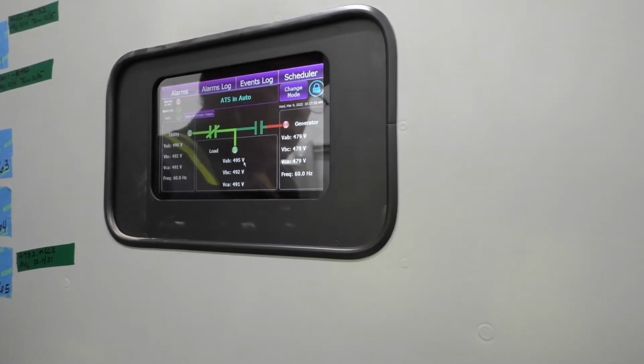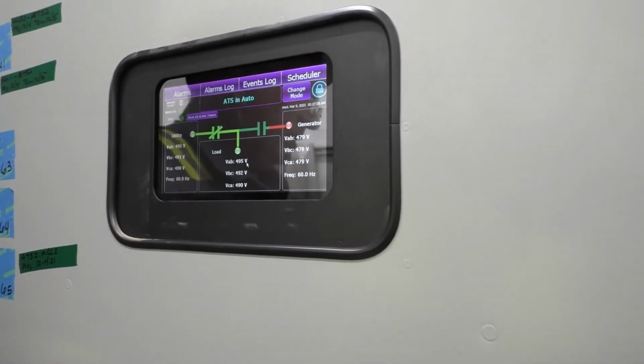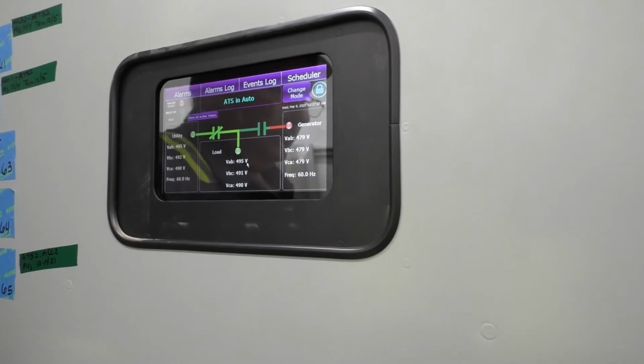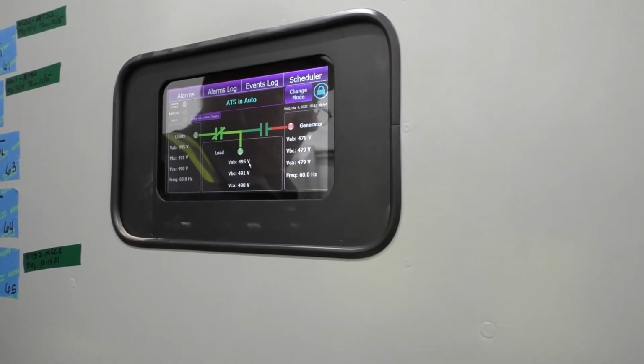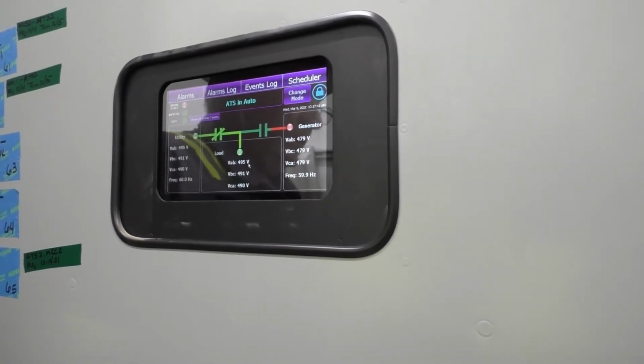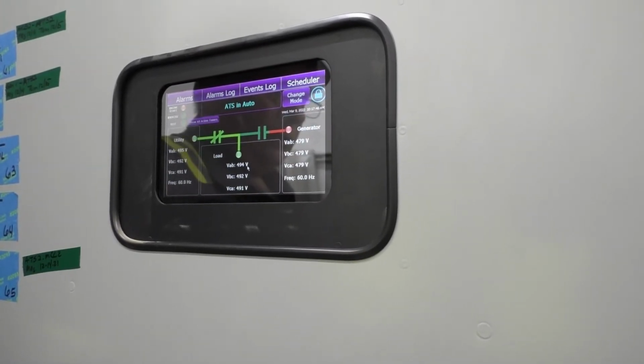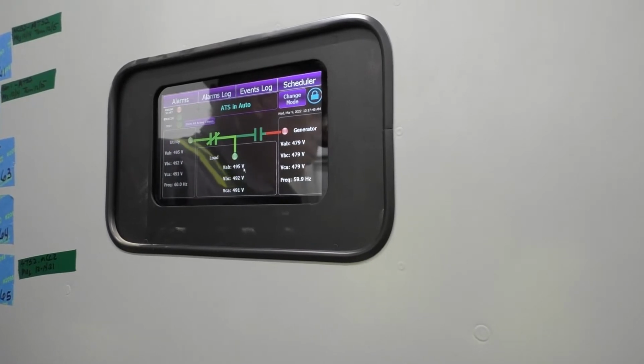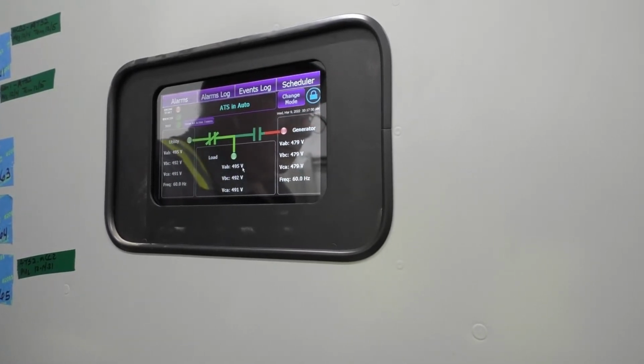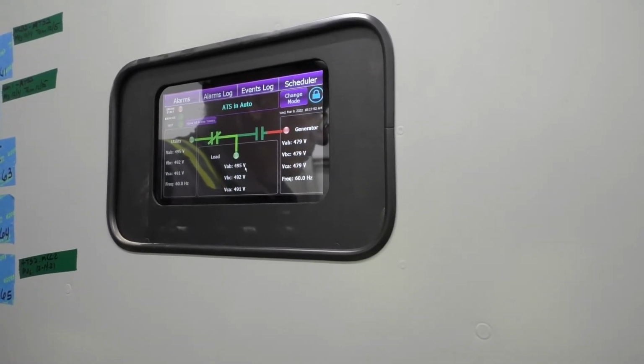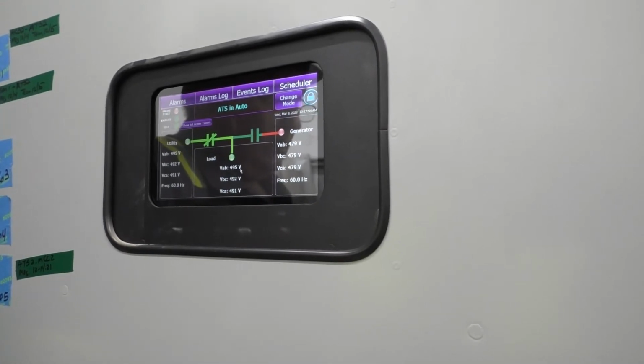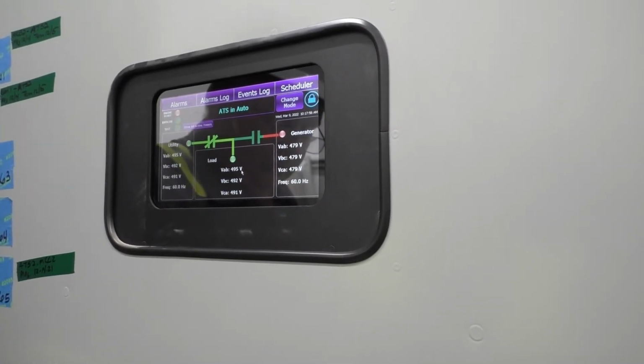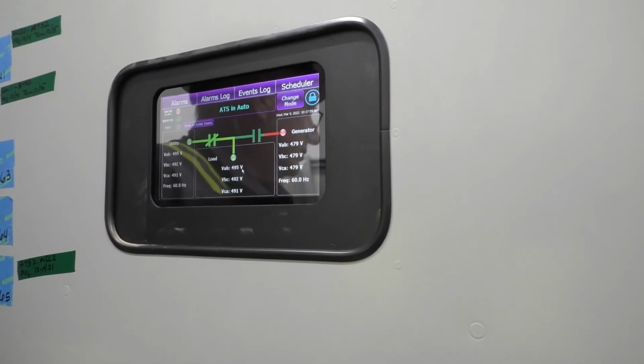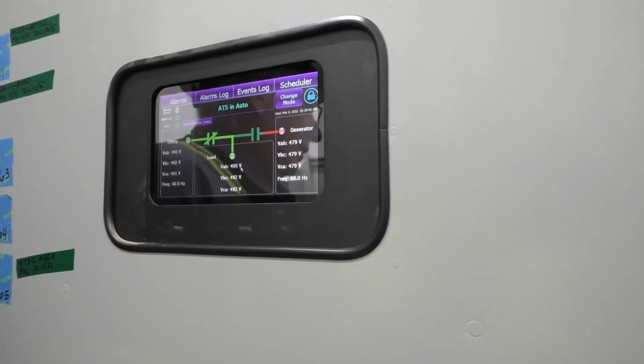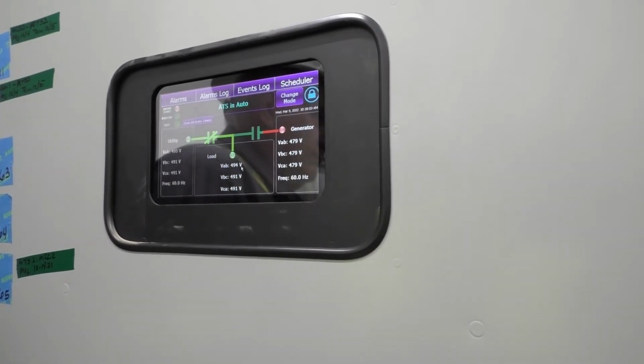It's pretty much it. We can set the exerciser if you give me a time and day of the week that you want to do it, or you may want to wait until the plant's operational. Is this thing operational? Not yet. That's what I thought. So you don't want it running yet, so it's not necessary. Okay. So we're going to leave the generator off, and the breaker open, so we don't interfere with any plant operations. And if you have an outage and need it, you can go out and restore it, and it'll pick up the buildings. Any questions? I know I talk kind of fast, but I know this stuff.